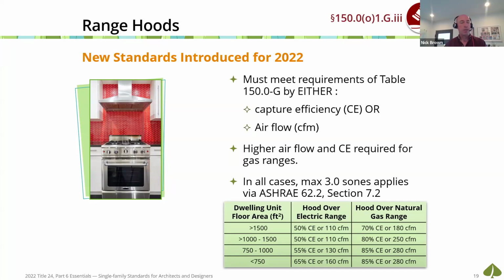And this was counterintuitive to me when I first saw it. A large home needs 110 CFM over an electric range. A small home needs more, 160 CFM. Why would that be? Because those pollutants you're creating are the same. You're cooking a given meal in a smaller home, those pollutants are higher concentration. There you go, Zach. So you need a higher rate of removal in a small apartment than you do in a large mansion. So this flies in the face of equity and affordability, of course, but it's what the building science says.